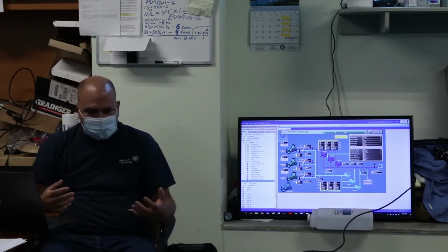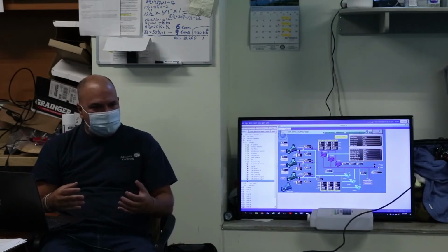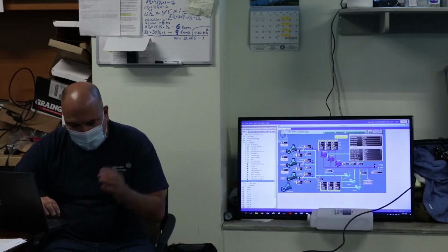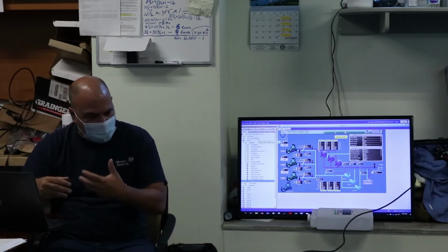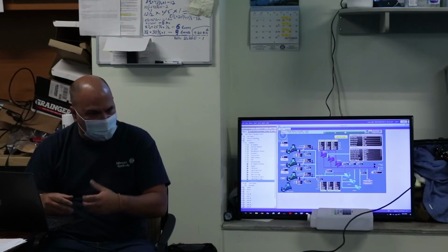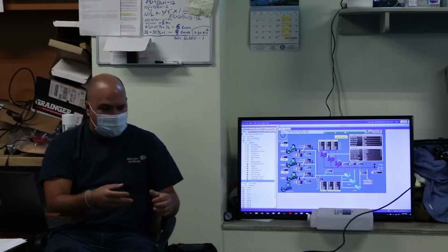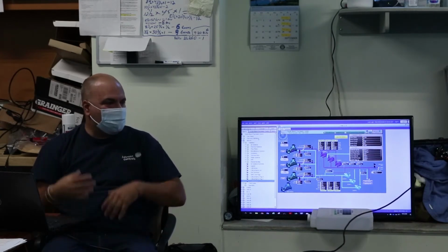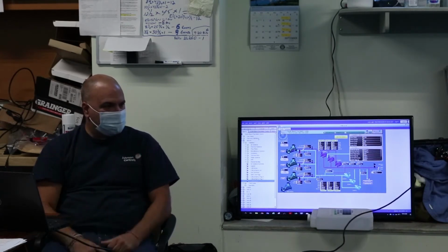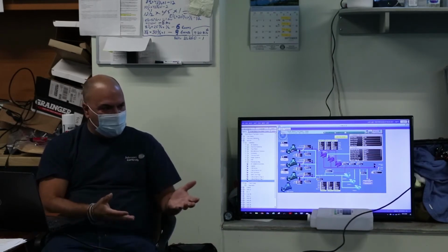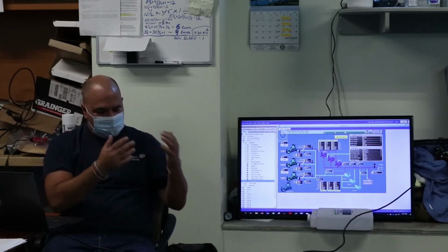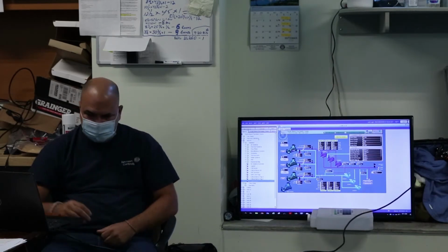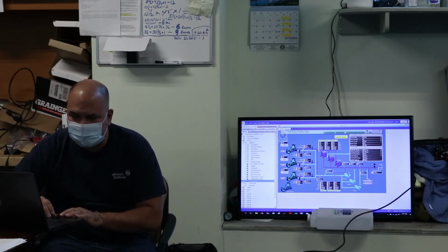So if you wanted to create a new graphics page, you would get the object, edit the page as you wanted, and then save it as a new Metasys object in whatever folder you wanted in the tree. That would give you a completely new page to look at. If you're going to do an existing page, you would open the object, edit it, and then save it to the existing page. I'm going to get rid of this because we don't need it.